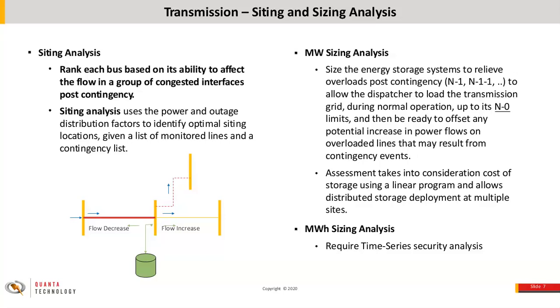On megawatt sizing, we size not only for the intact or normal system, but we also need to account for contingencies. Megawatt-hour sizing needs to take the time element into account, so we end up doing time series power flow and time series contingency analysis, which is very time consuming but necessary.